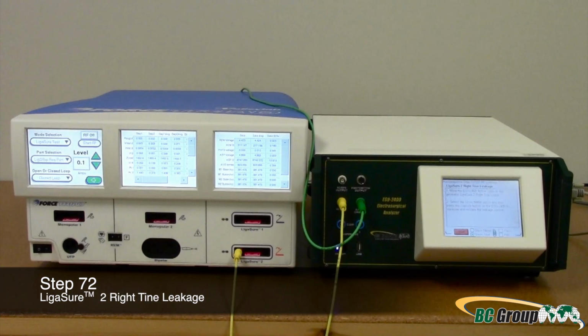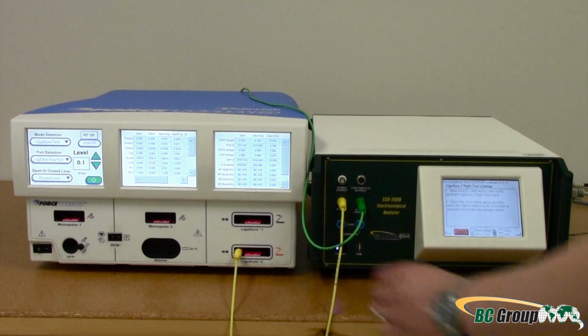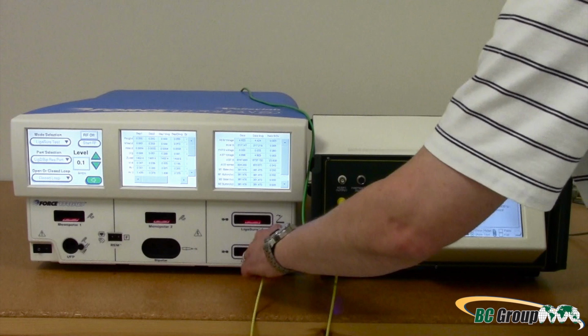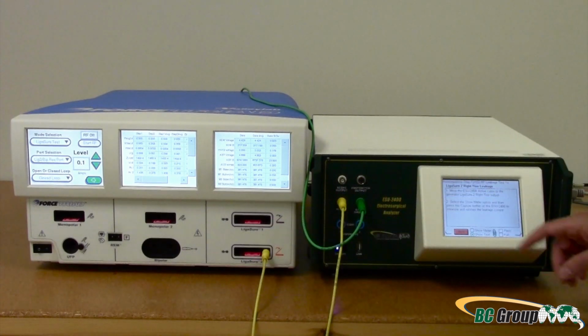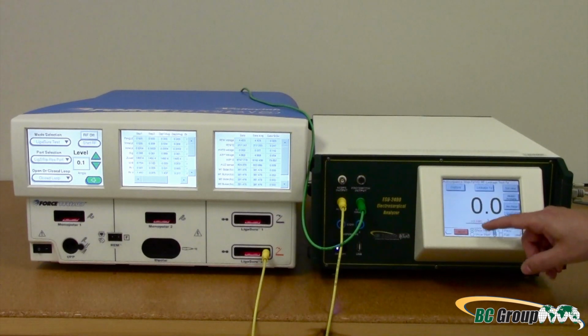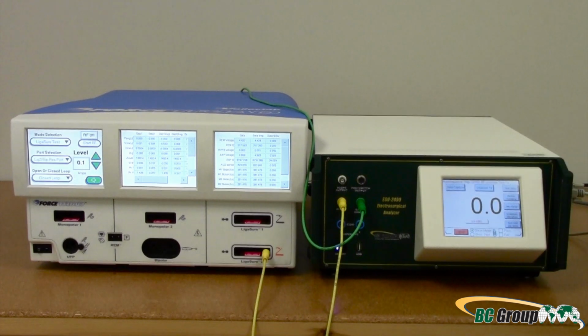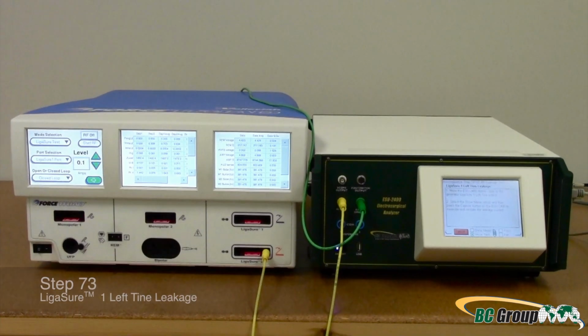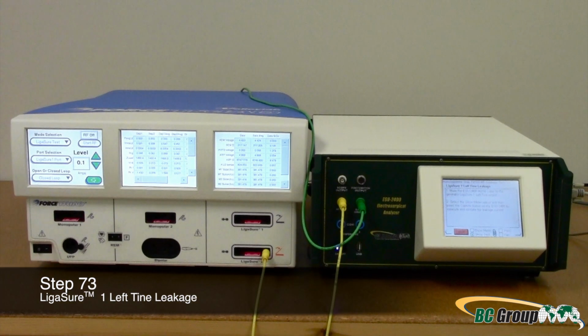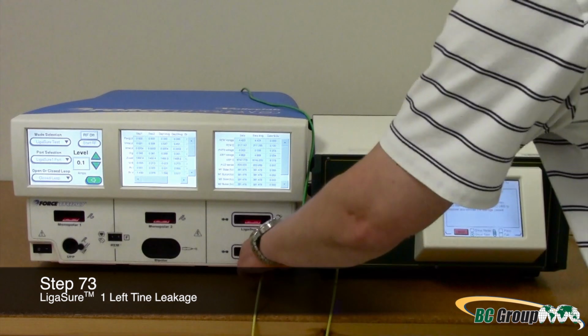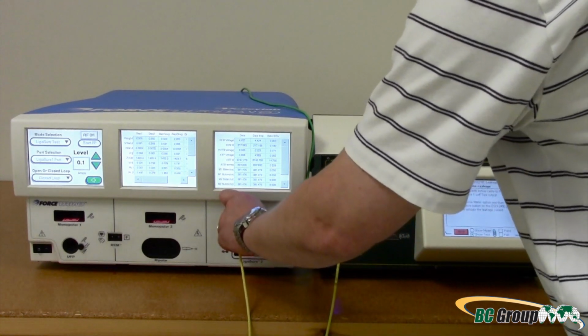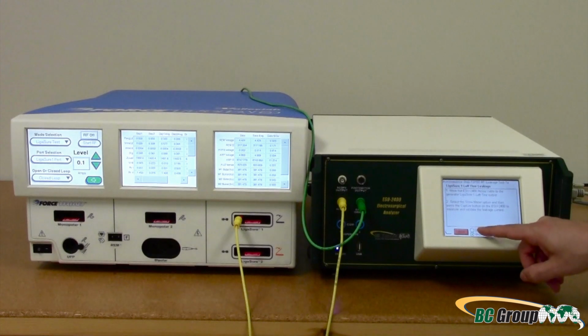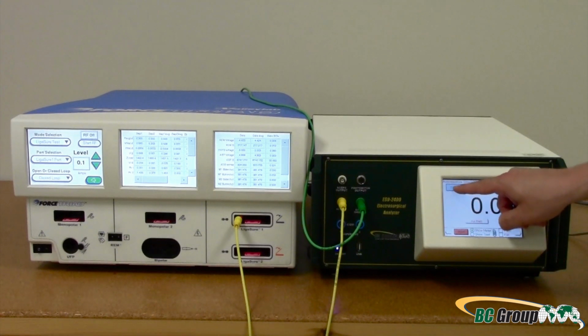Step 72. LigaSure 2 right tine leakage. Move the ESU-2400 active cable to the right tine of the LigaSure 2 port. Select Show Meter and then press Capture. Step 73. LigaSure 1 left tine leakage. Move the ESU-2400 active cable to the left tine of the LigaSure 1 port. Select Show Meter and then press Capture.